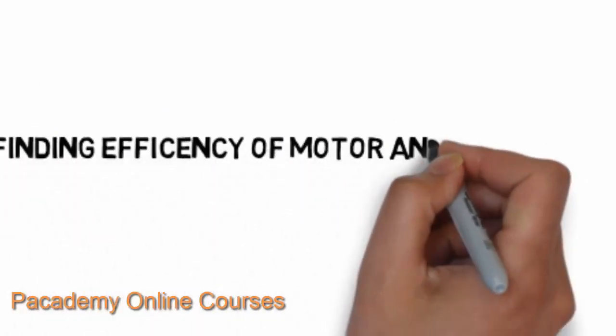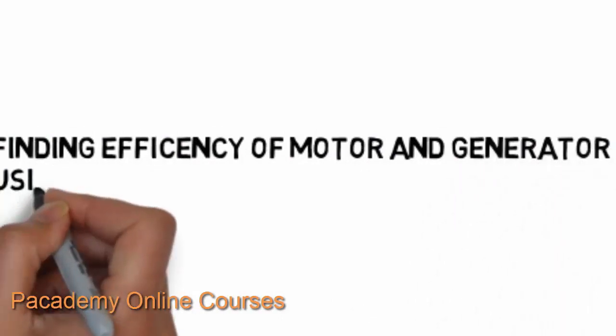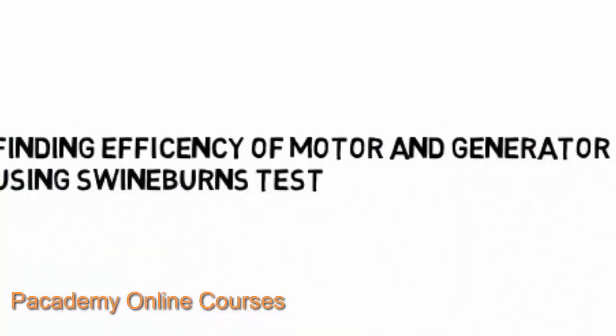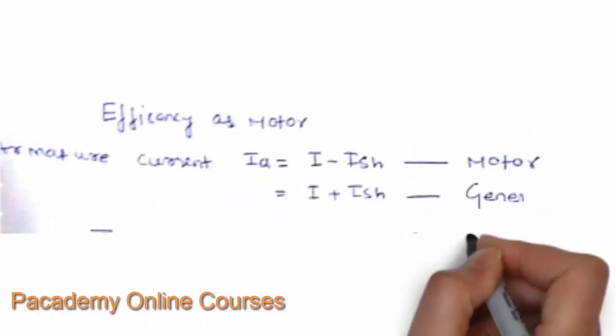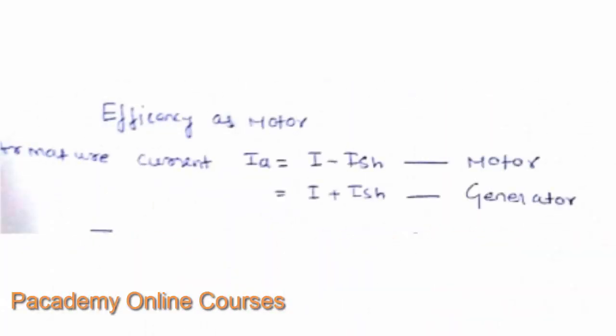Now, how do you find the efficiency of the motor and the generator using these test results? To find the motor efficiency, the armature current IA is taken as I0 minus ISH. For the generator, IA is I0 plus ISH — supply current plus field current — because the generator is outputting current.